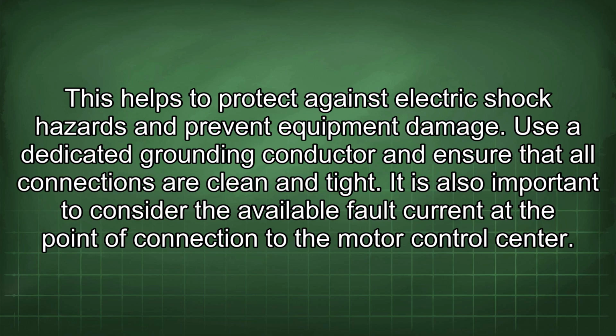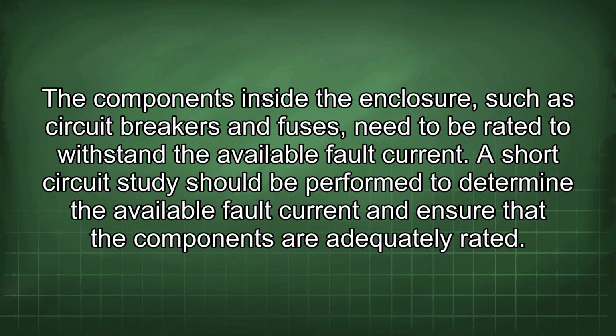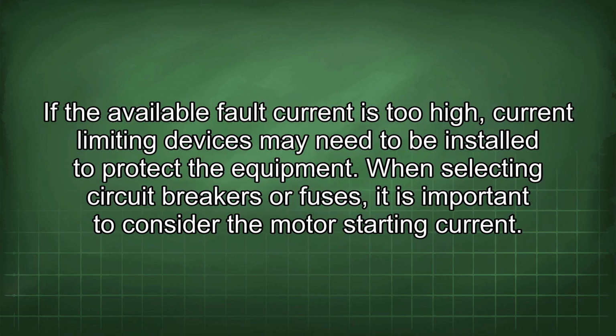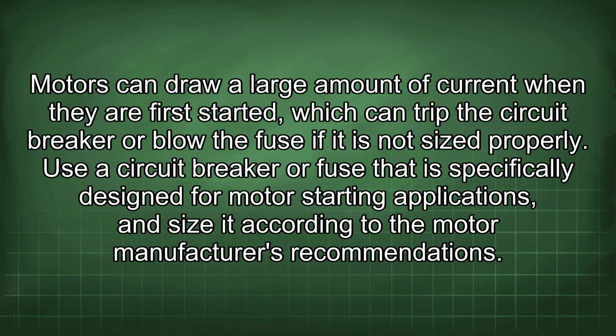It is also important to consider the available fault current at the point of connection to the motor control center. The components inside the enclosure, such as circuit breakers and fuses, need to be rated to withstand the available fault current. A short circuit study should be performed to determine the available fault current and ensure that the components are adequately rated. If the available fault current is too high, current limiting devices may need to be installed to protect the equipment. When selecting circuit breakers or fuses, it is important to consider the motor's starting current. Motors can draw a large amount of current when they are first started, which can trip the circuit breaker or blow the fuse if it is not sized properly.